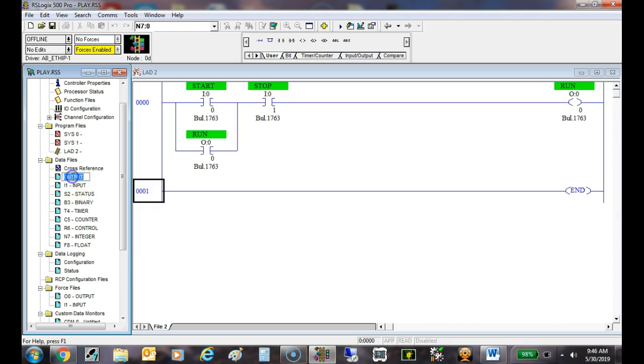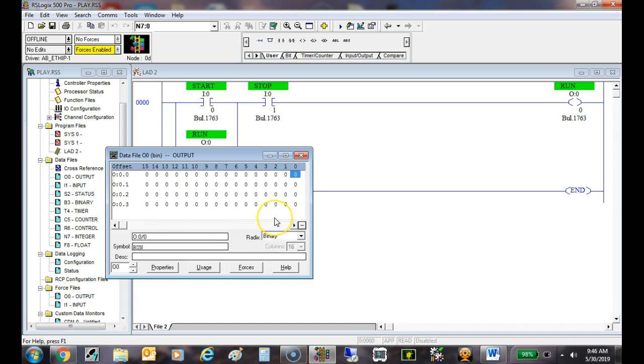The output data block basically shows us the status of our inputs and our outputs. Right now I can look at this and tell all my outputs are turned off, because if one was turned on, there would be a 1 in the associated bit. Also, Allen-Bradley PLCs work in groups of 16 bits. Notice the groups run from 0 to 15. We call them module numbers, but technically they might not be modules. Every group of 16 on an input port or an output port would get another module number.